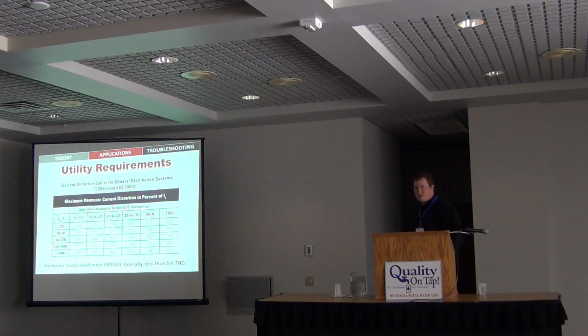Now there are other loads within your plant that are not harmonic loads, such as unit heaters and loads of that nature that are linear. But normally that quantity or that ratio of linear load does not negate the amount of harmonics produced by VFDs, especially in a water, wastewater plant or small pump house, well house, and things like that.